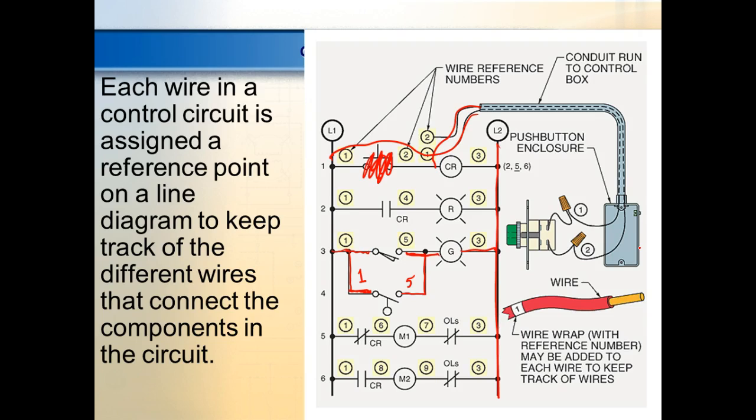You understand? So you're going to run into a lot of wire numbers. The biggest problem we have with our students is trying to give these common spots different numbers. I'll see people do that. They'll come down here and do wire numbers. They'll start 1, 2, 3, 4, 5, 6, 7, 8, 9, even though this is the same spot. So electrically, this right here is the same. These all right here are electrically the same, right? You understand that?